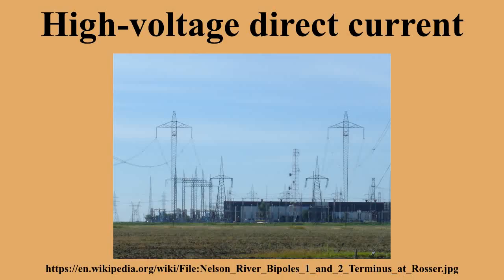HVDC can transfer power between separate AC networks. HVDC power flow between separate AC systems can be automatically controlled to support either network during transient conditions, but without the risk that a major power system collapse in one network will lead to a collapse in the second. HVDC improves on system controllability, with at least one HVDC link embedded in an AC grid, in the deregulated environment. The controllability feature is particularly useful where control of energy trading is needed.